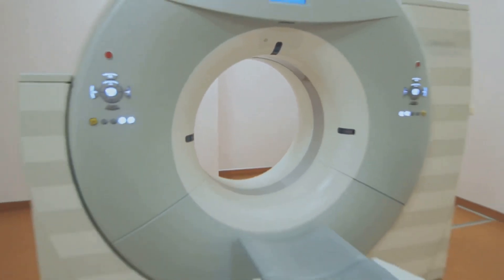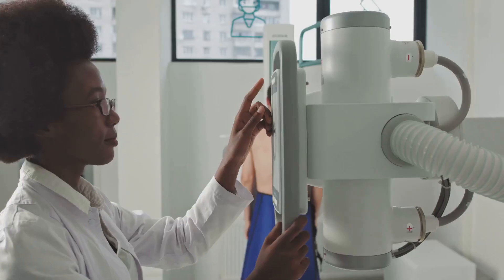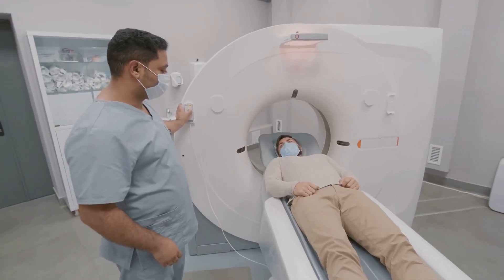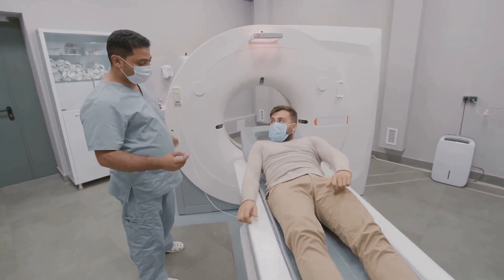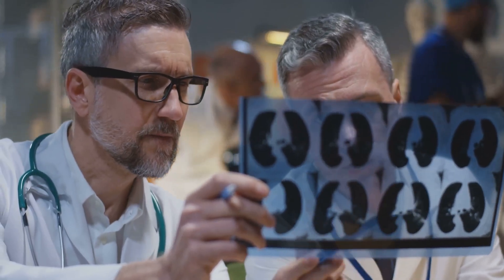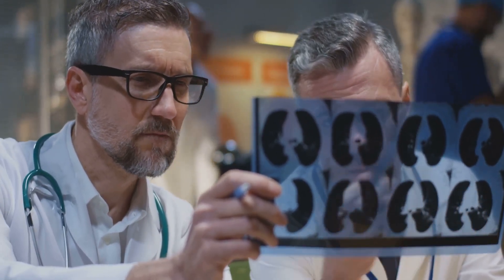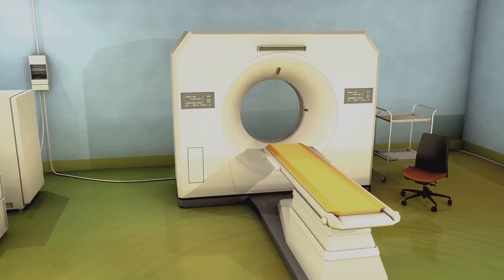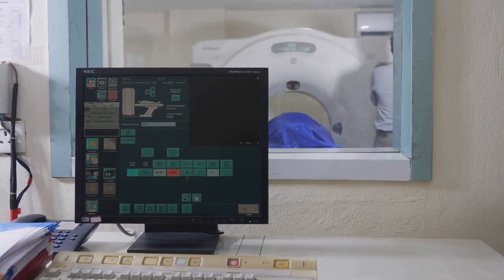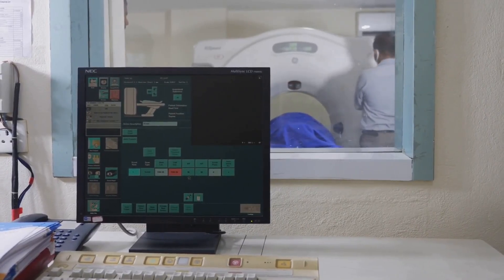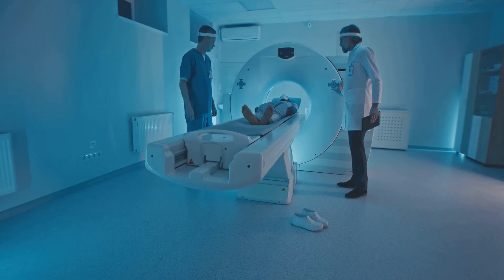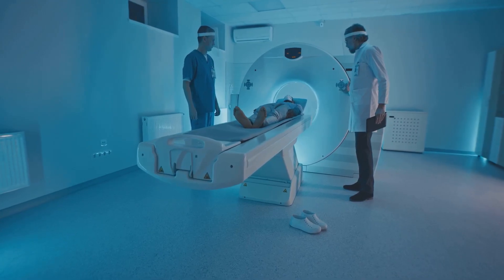The x-ray tube generates the x-ray beam that penetrates the patient's body. The tube's performance is crucial for image quality and diagnostic accuracy. Situated opposite the x-ray tube within the gantry, the detector array captures the x-rays that pass through the patient, converting x-ray photons into electrical signals to form the basis of the CT image. The slip ring allows for continuous rotation of the gantry by transmitting power and data to the rotating components. The operating console is the interface for technicians to control the scanner, input patient data, initiate scans, and view and manipulate images. Understanding the interplay between these components is essential for diagnosing issues.